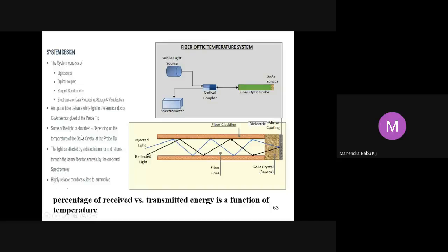Some of the light is absorbed here. So the light which is coming out of the source passes through this optical, and then it passes through a fiber optic probe. This optical fiber delivers a white light to a semiconductor sensor here, which is glued to the probe tip. Some of the light is absorbed depending upon the temperature at the tip of the probe, and the light is reflected by a dielectric mirror and returns through the same fiber for analysis on the onboard spectrometer.